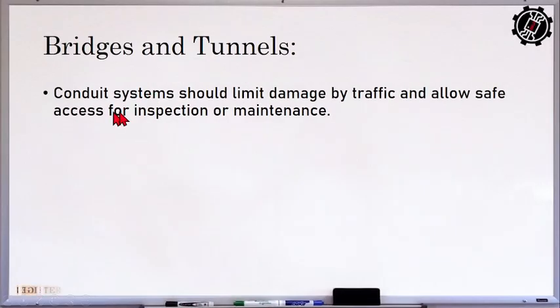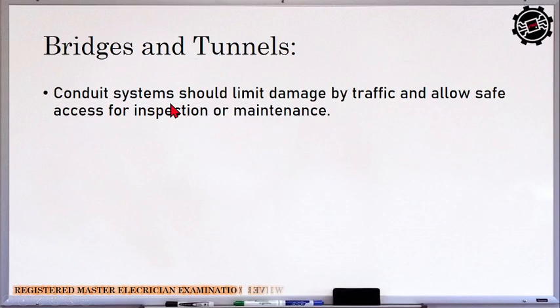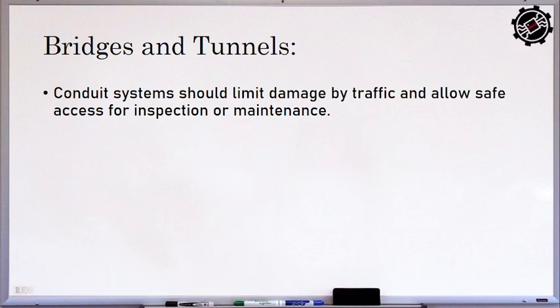So, bridges and tunnels: the conduit system should limit damage by traffic and allow safe access for inspection or maintenance. If our conduit system is under a bridge or in a tunnel, it must be installed sturdily enough that it is not easily damaged. For example, if a truck runs over it, our conduit system will not easily be destroyed, or it is placed below the roadway or bridge where vehicles and trucks cannot affect it. But it is also safe enough to be inspected and maintained by our qualified personnel.